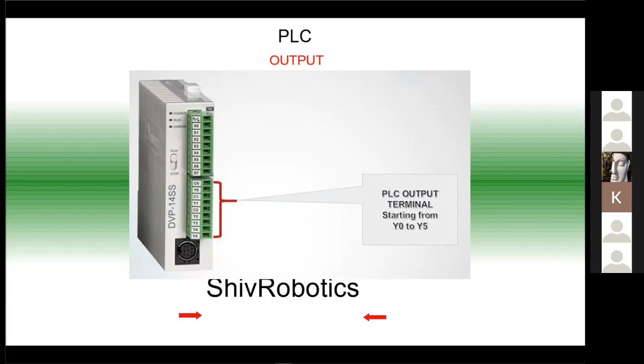If this is the case, then we need to carefully choose the PLC. The PLC can offer you solid state type outputs, where a transistor or MOSFET will be used to drive the outputs. Open collector type, where the output is going high or low whenever it is triggered. If it is not triggered, it will be in the open condition. Or even relay controlled outputs are also there. The relay controlled outputs will not directly take the load, but the relay is connected to the contactor, and from the contactor it is connected to a motor.